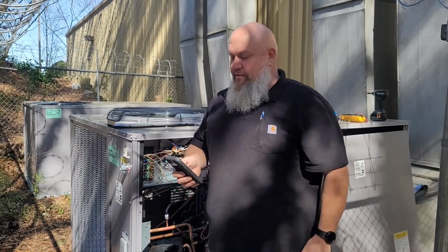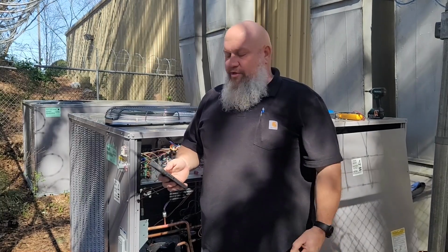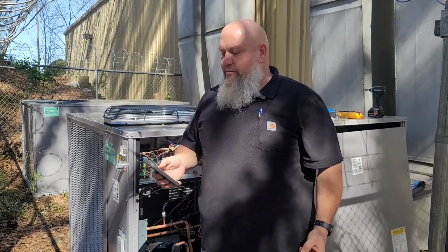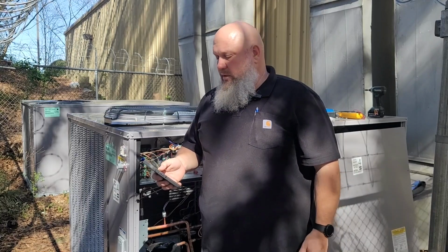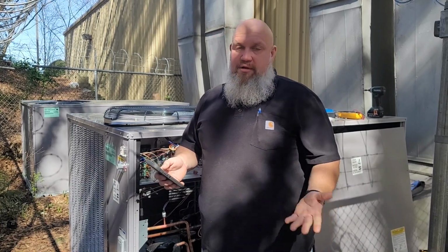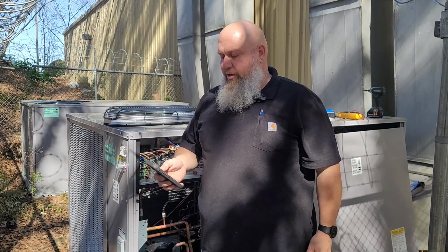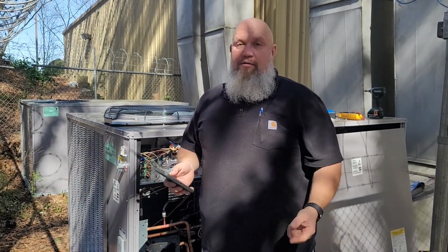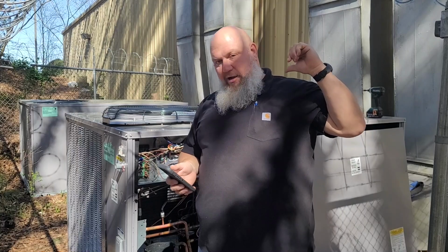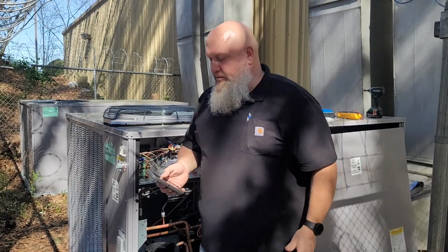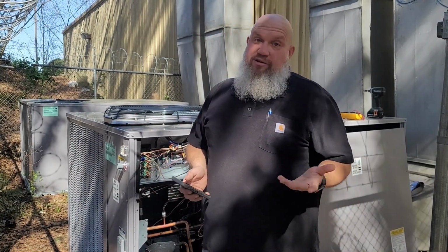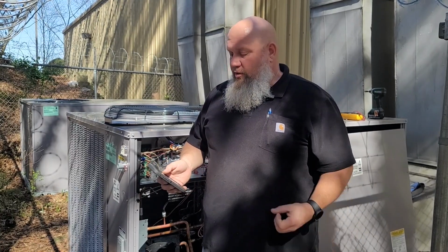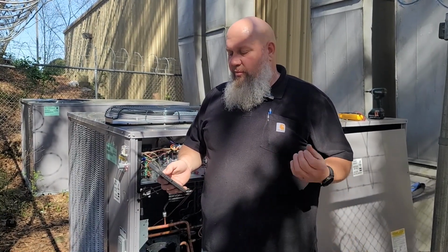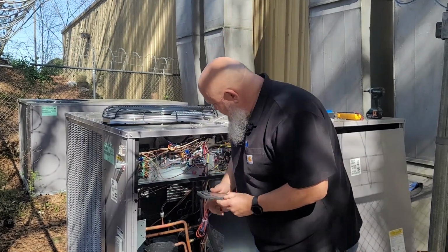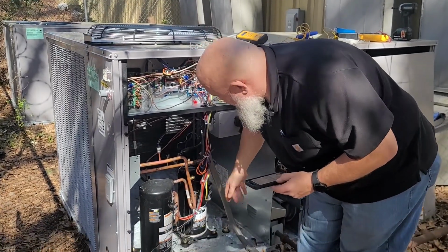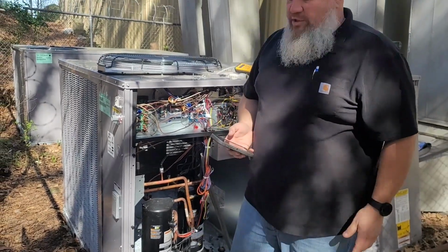And this is all a checklist in the software. All the gas piping's been checked for leaks. Electrical connections are properly torqued. Gas pressure of the unit valve at the unit is within specs. The return air filter on the outside, make sure that's installed and it's clean. Making sure the unit's level. Blower wheels, everything spins properly. There's no wiring touching any of the copper, rubbing up against it. You never know, units in shipping.